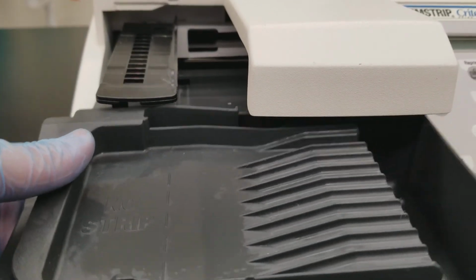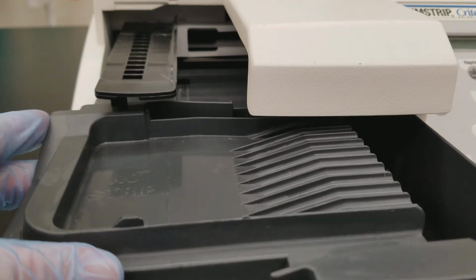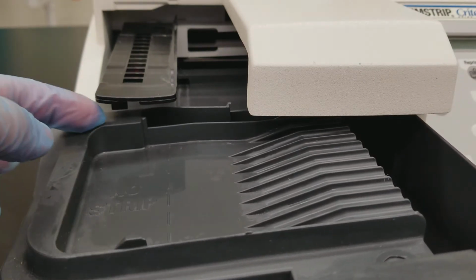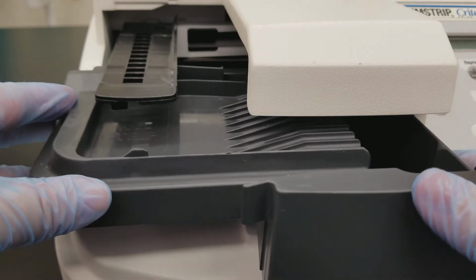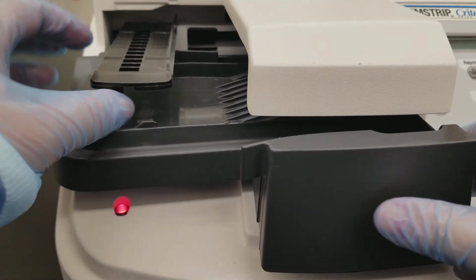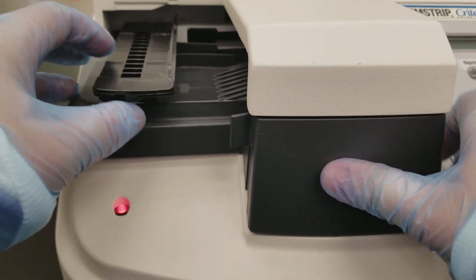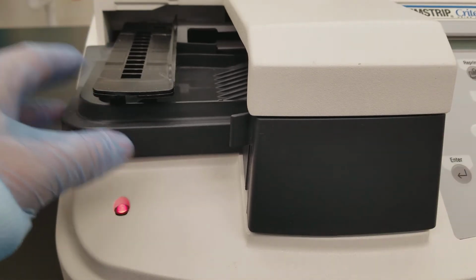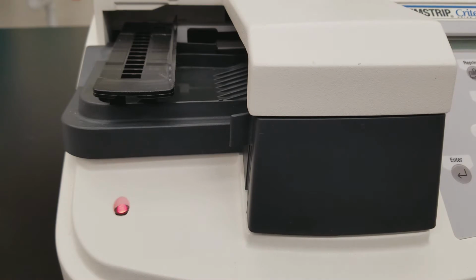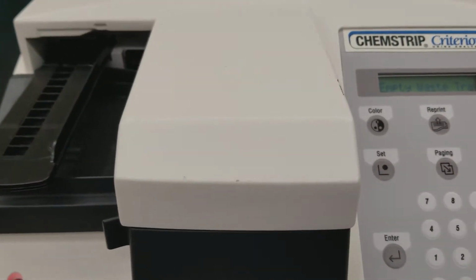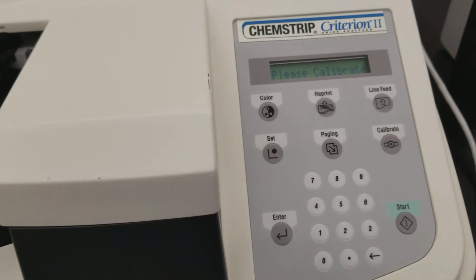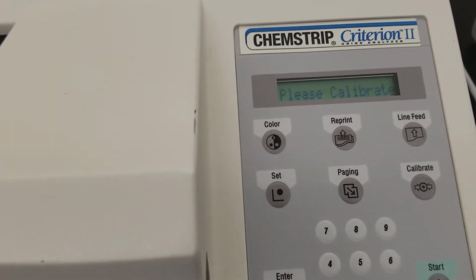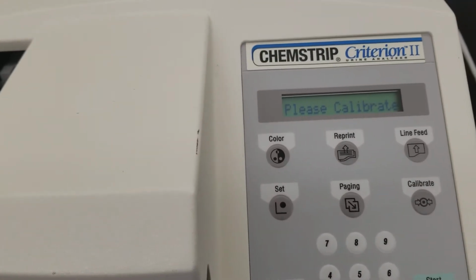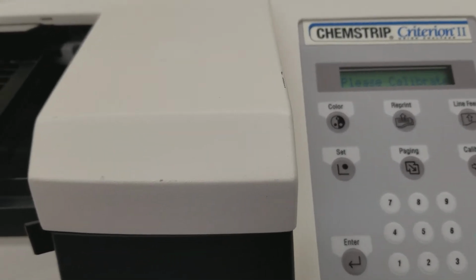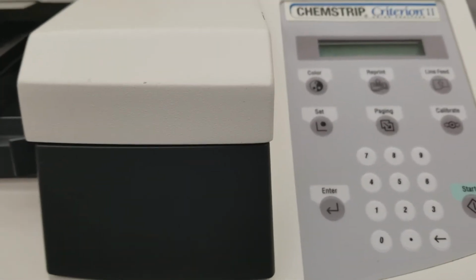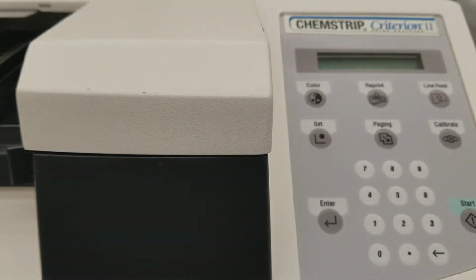Same thing when you go to push it in, everything is gentle. This little lip right there is going to need to be lifted up over. You slide in, and then again, lift gently. Everything is super gently, please. This is almost like an antique now. All right, so we emptied the tray, and now we're going to press start, and it's going to tell us, hey, you can't do anything until you calibrate.